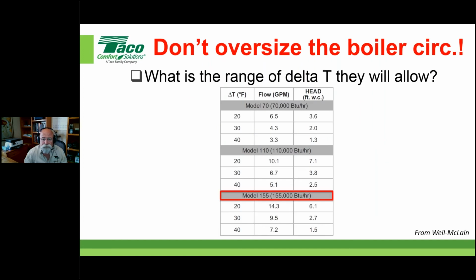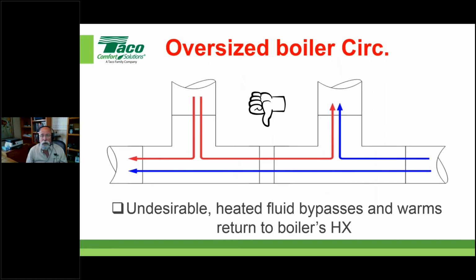One question was about whether that would induce short cycling. Oh, absolutely, depending on what that temperature is and how far that boiler was able to turn down or not, different boilers, different things. But yes, good point to make. We're not only talking about overall system efficiency, but steady state efficiency. We really don't want that boiler banging on and off, and that's a whole other webinar we'll probably do down the road when we talk about buffer tanks and things like that.